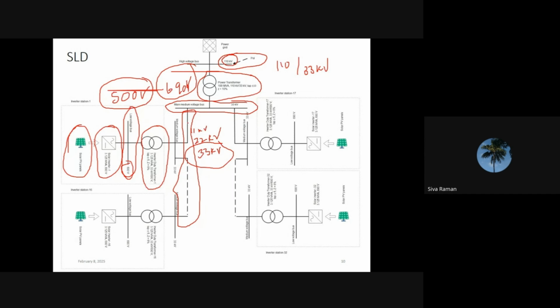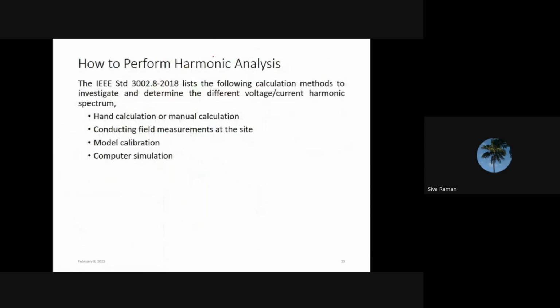Generally, this collector network may be a cable or a 33 kV transmission line, sometimes a combination of both. And it will have a power transformer that steps up from 33 kV to 110 kV. So 110 kV is the interconnection voltage, and there we get connected to the transmission system. From there we export the power to the power grid.